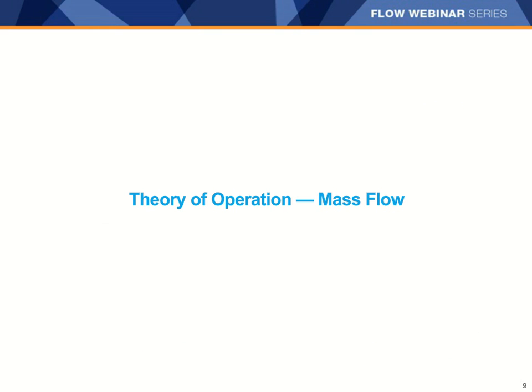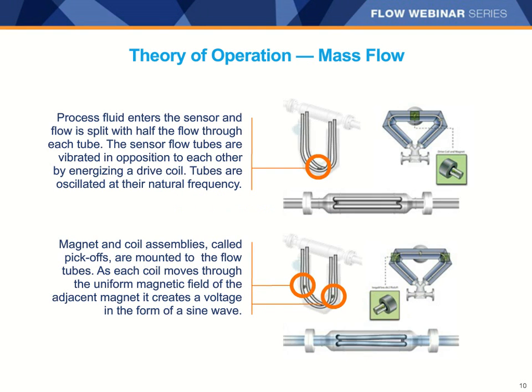Let's start by looking at how Coriolis meters measure mass flow. All of our meters work in a similar way. The material to be measured enters the meter through the process connections and passes through a flow splitter that divides the material equally between the measurement tubes. 100% of the material passes through the measurement tubes. There is no slipstream inside the meter. The manifold and end connections of the meter provide a rigid structure to mount in your pipeline while isolating the measurement sections of the meter from any outside noise.